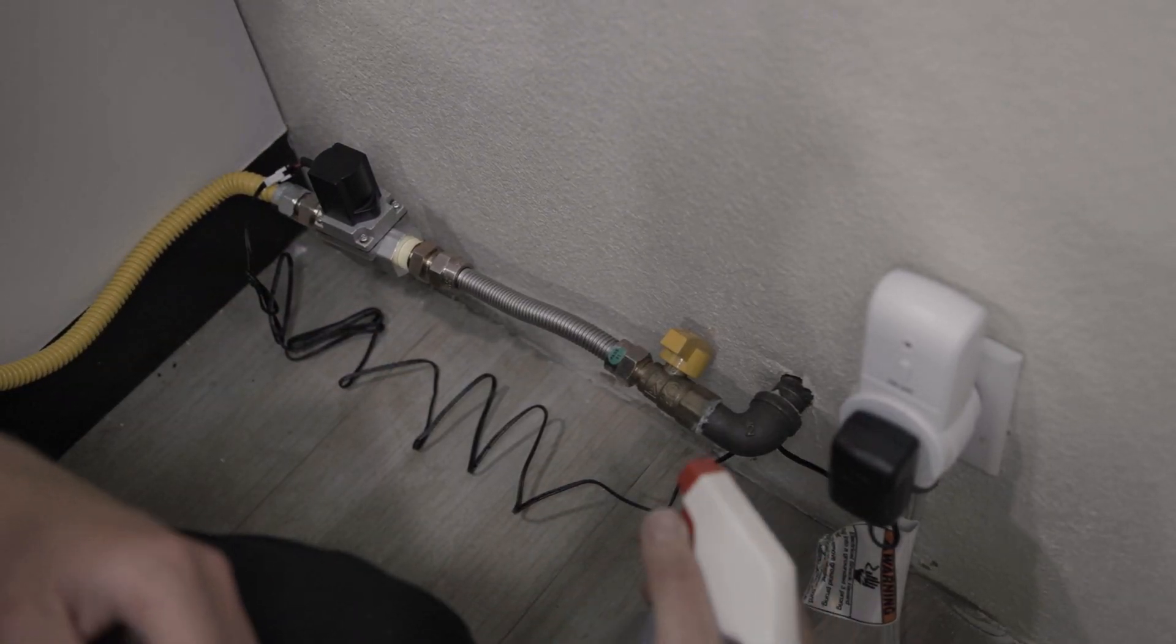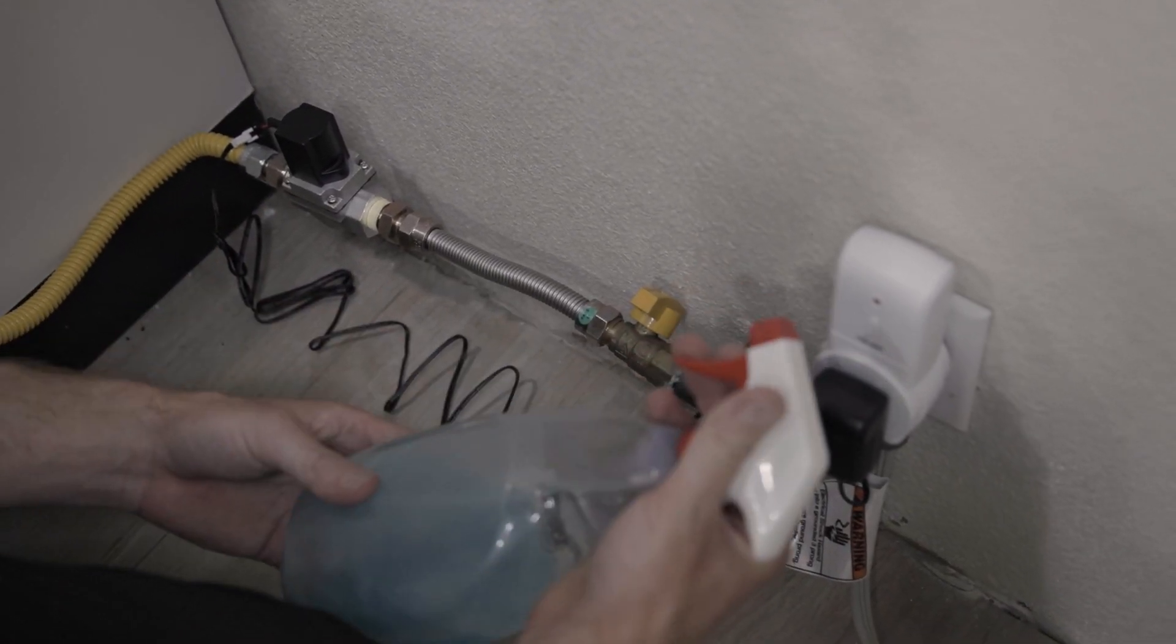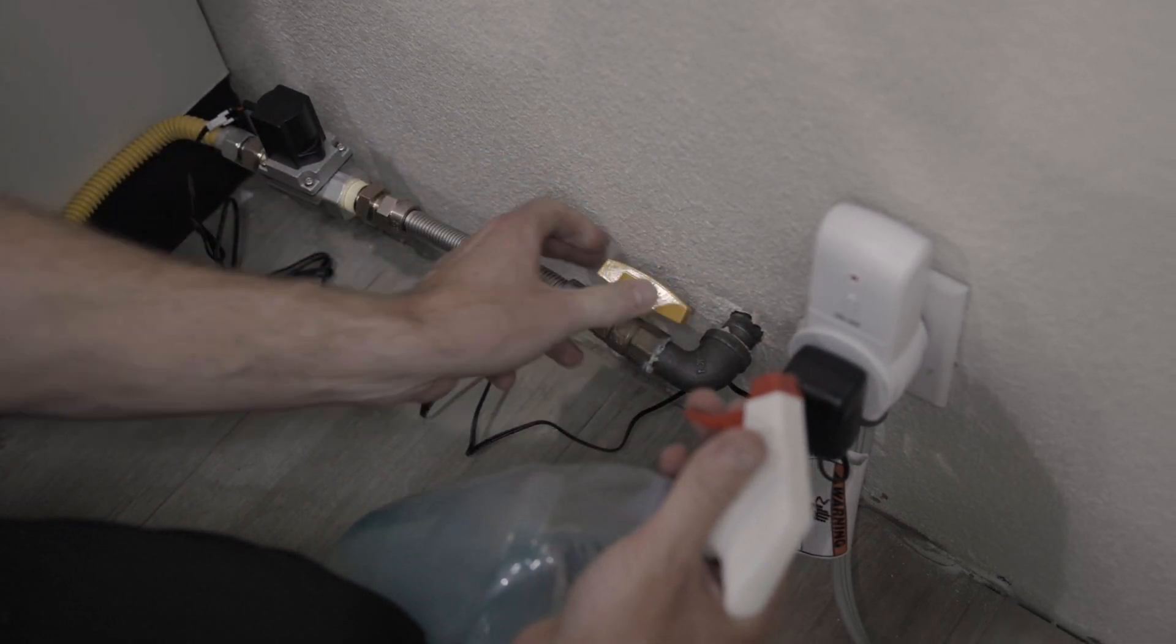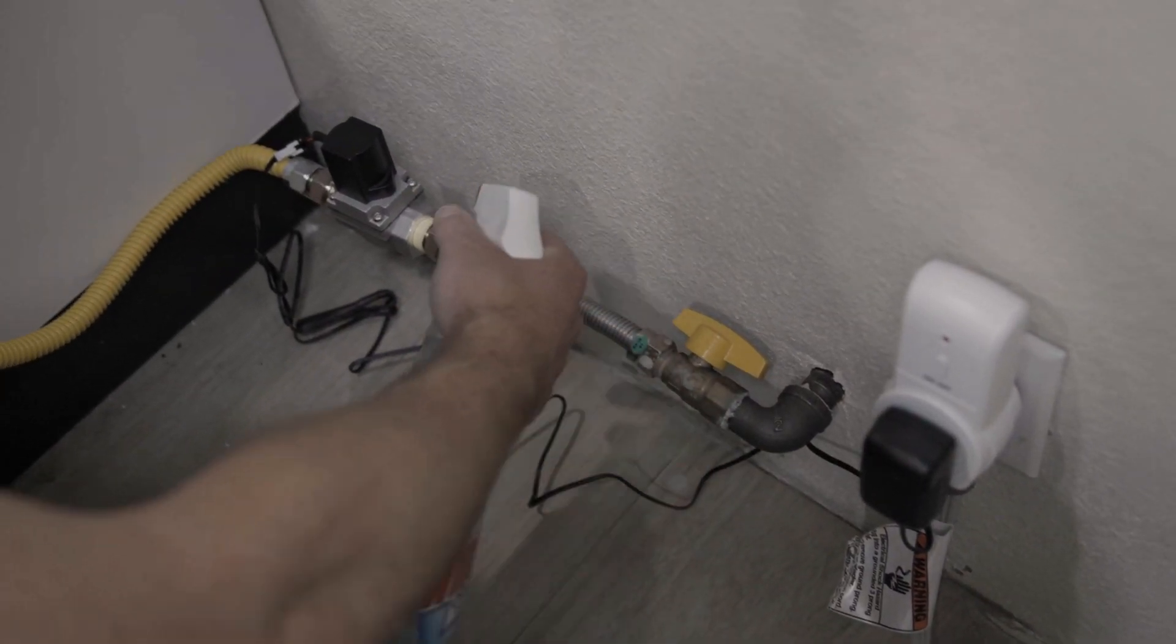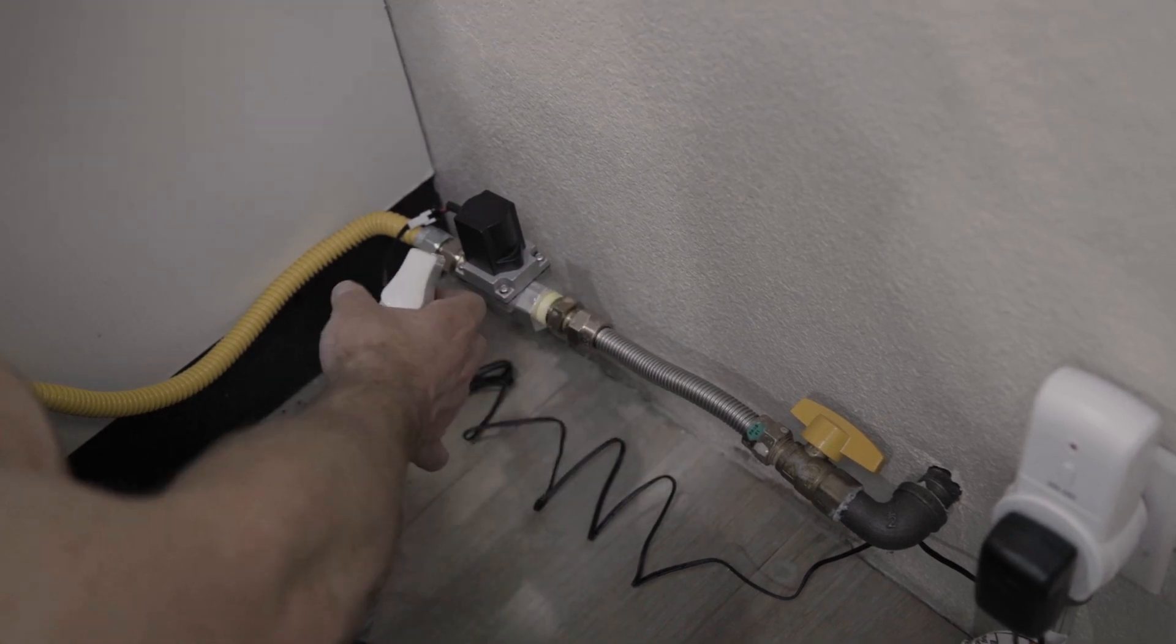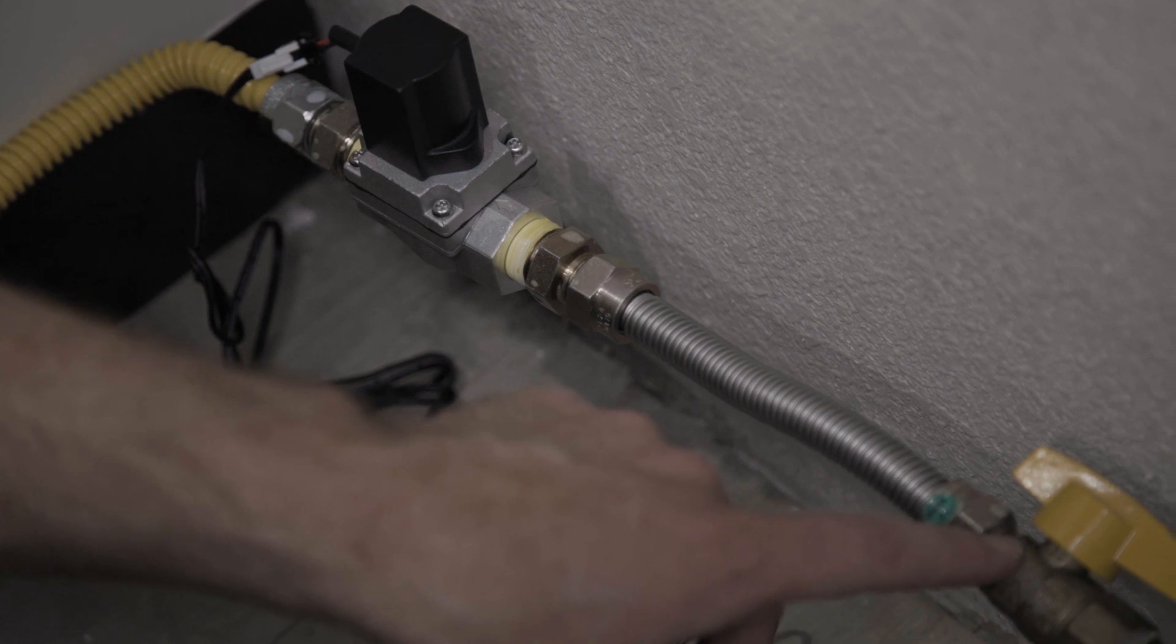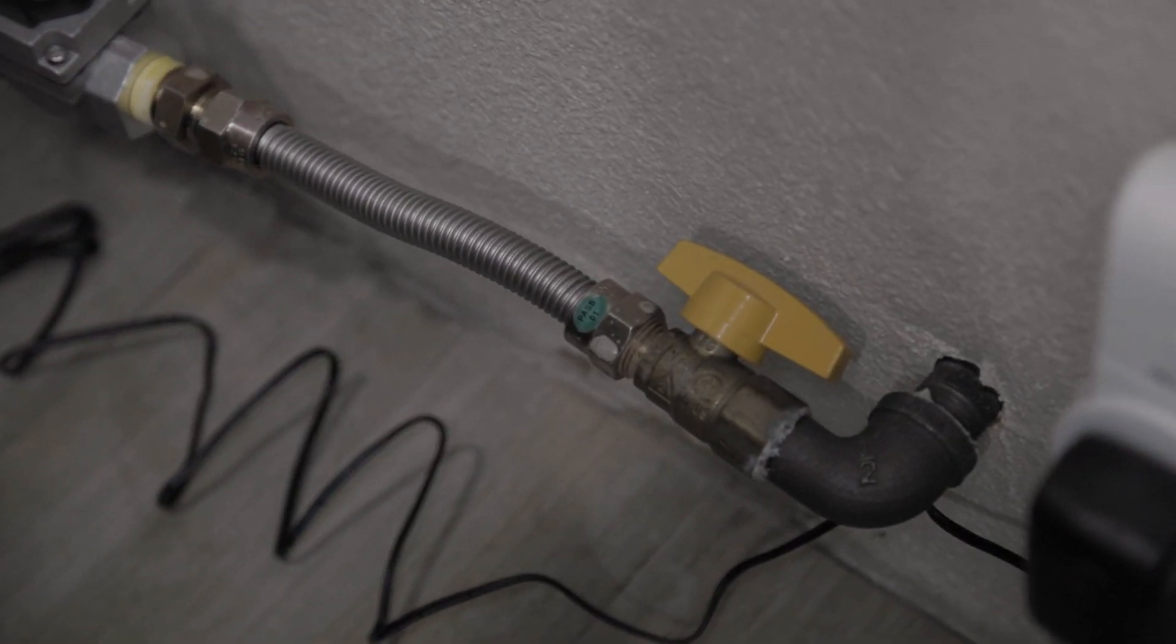After you're done testing the solenoid, use a gas leak detection liquid. Turn your gas line back on and you're going to spray that on the joints to make sure there's no gas leaks. Typical gas leak can be seen by bubbles forming around the threads.